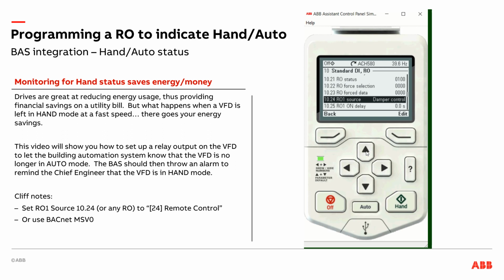And let's say I'm going to change relay output 1. So my factory default settings, relay output 1 is damper control, relay output 2 is running, and relay output 3 is whether I'm faulted or not. So let's say I'm not using a damper, so I'm going to borrow that relay. I'm going to repurpose it. I'm going to go in here and edit relay output 1.